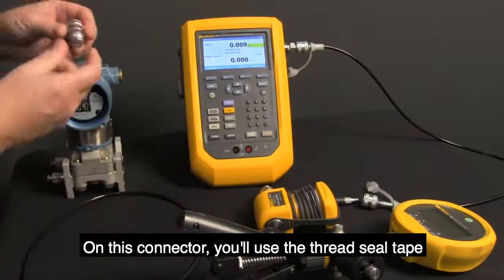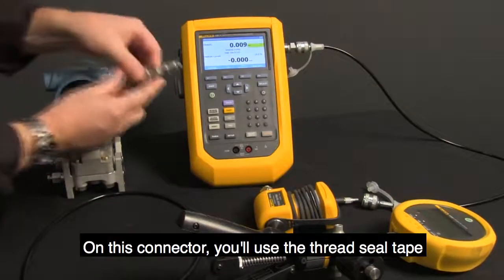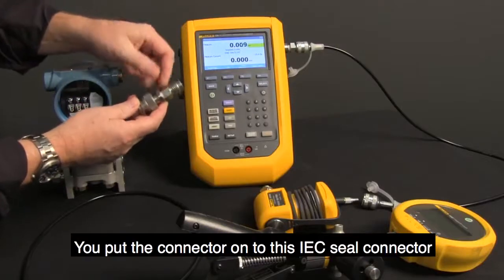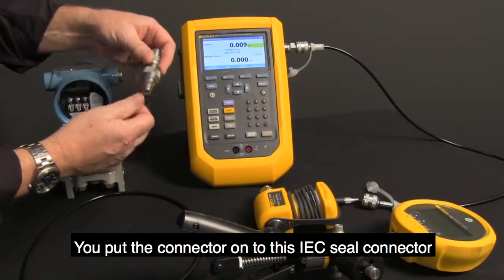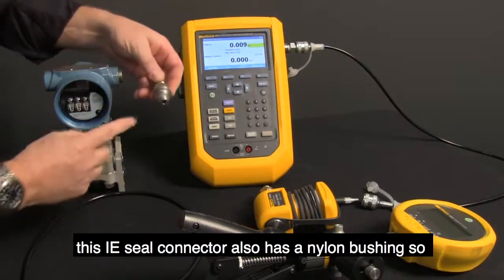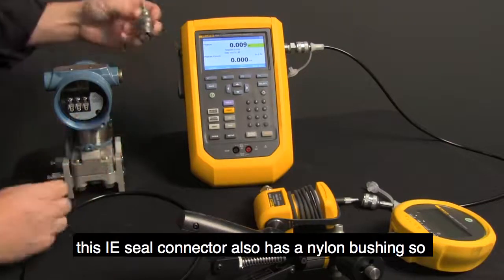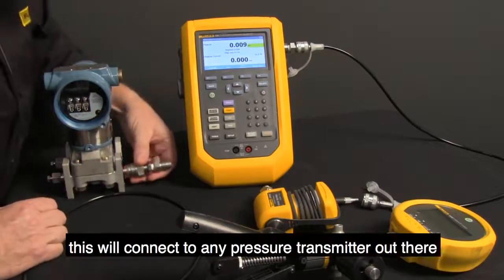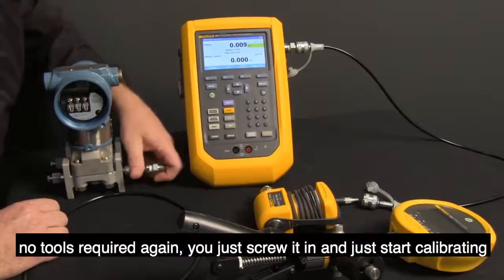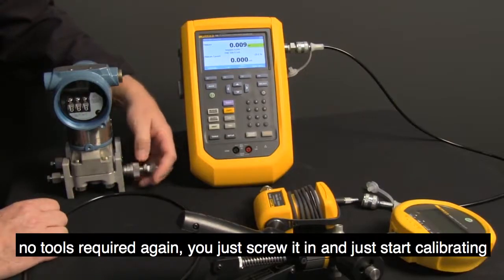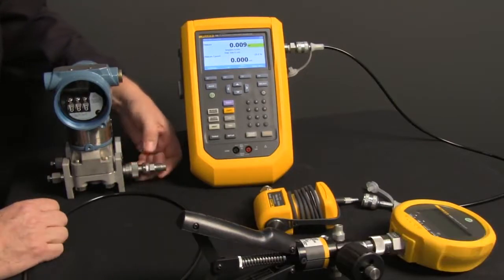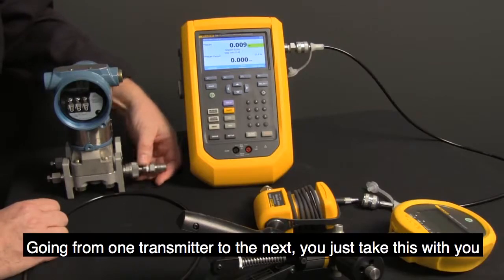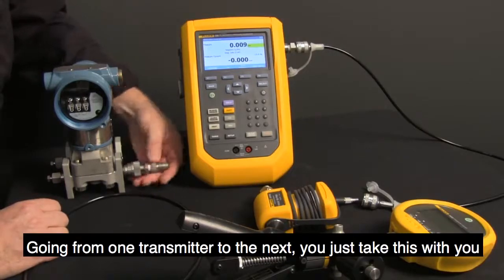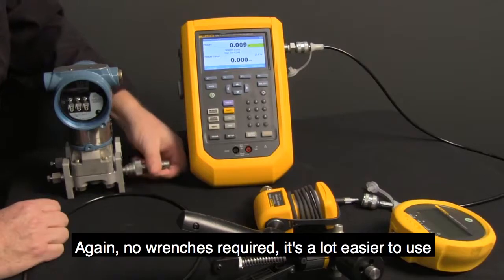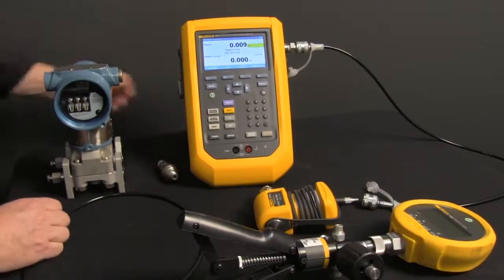On this connector, you use the thread seal tape. You put the connector on to this IEC connector. This IEC connector also has a nylon bushing, so this will connect to any pressure transmitter out there. No tools required again. You just screw it in and start calibrating. Going from one transmitter to the next, you just take this with you. So again, there's no wrenches required. It's a lot easier to use.